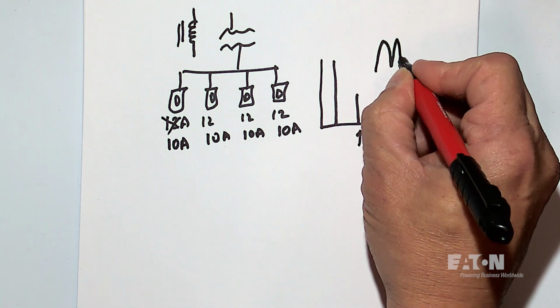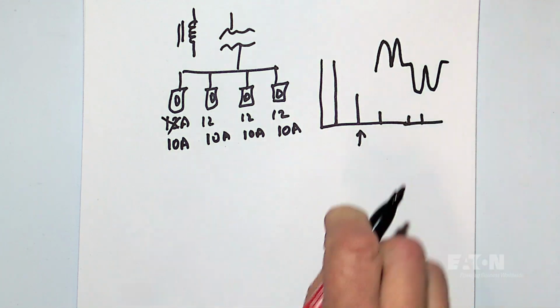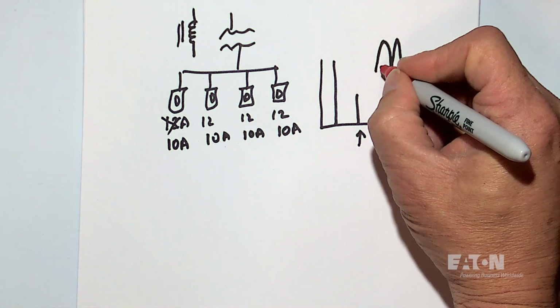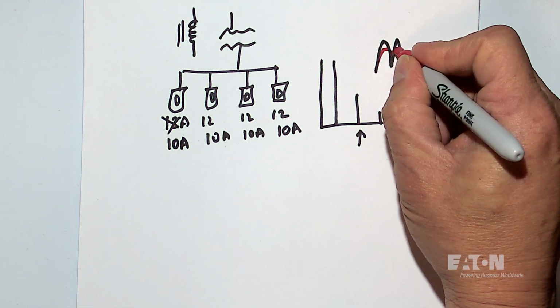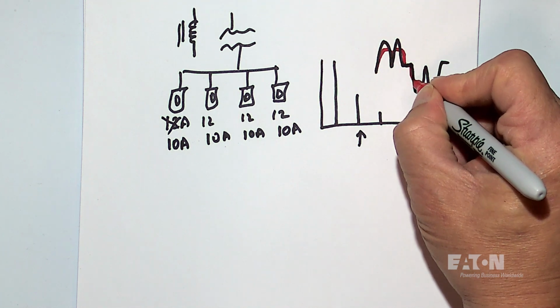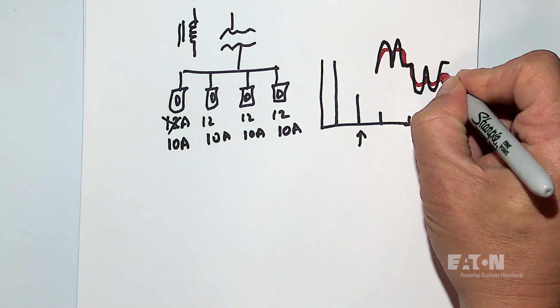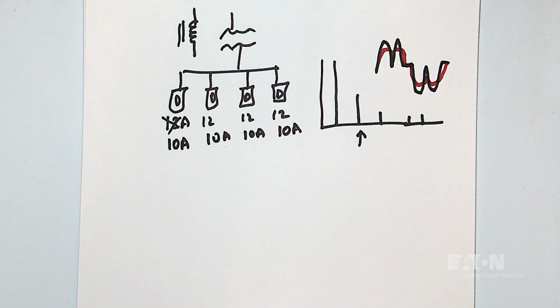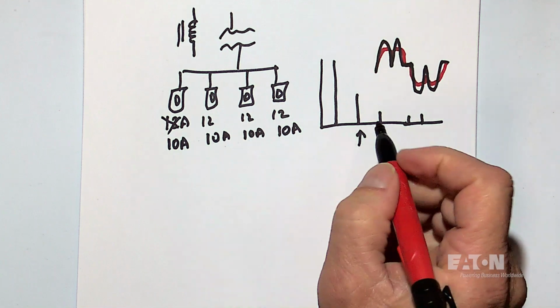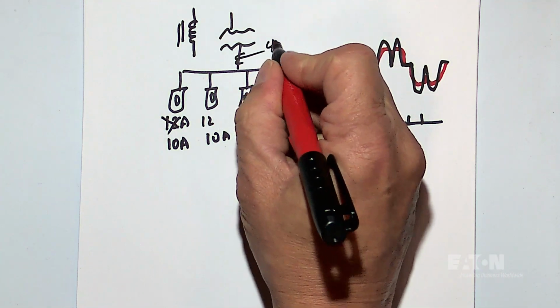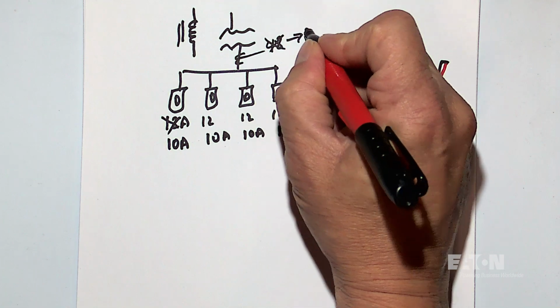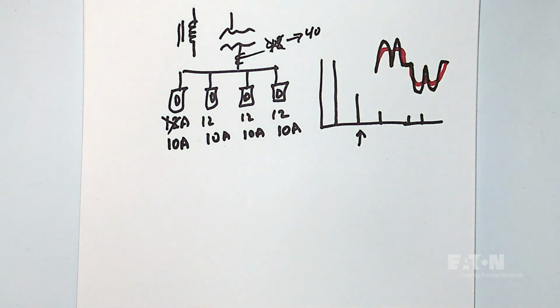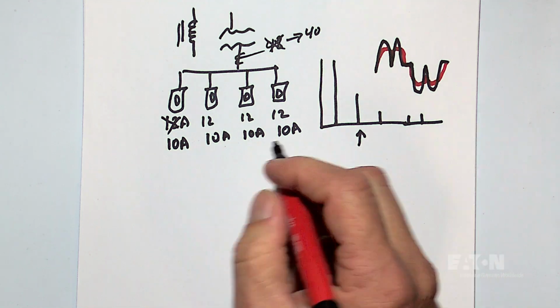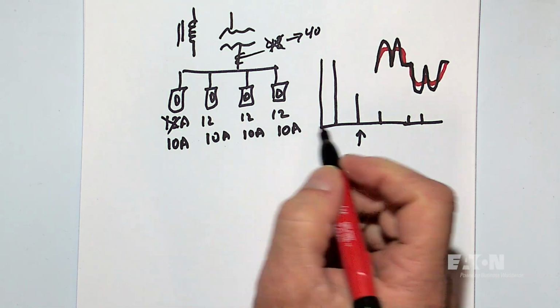So if I have a steep current that looks like this, when I put a line reactor on, I essentially get something that looks like this. It spreads it out a little bit, and it reduces the overall steepness of that. So that line reactor, being the transformer, reduces my overall harmonic current. So instead of being here 48 amps, it's more like 40 amps. And again, this is something that you probably wouldn't think about if you just thought about one drive by itself and you modeled this in a program, and the model is going to take 12 for every one of these, but in reality it's going to be less.